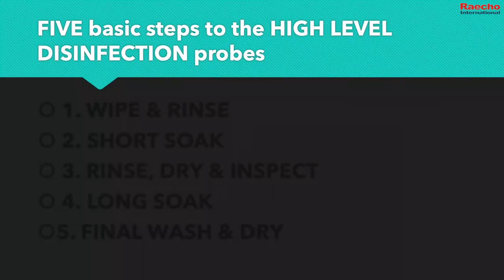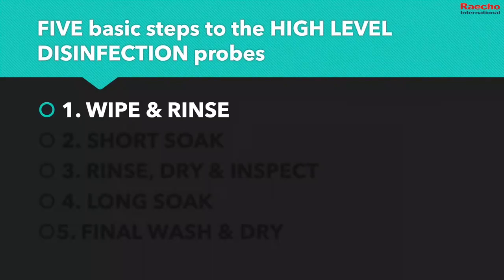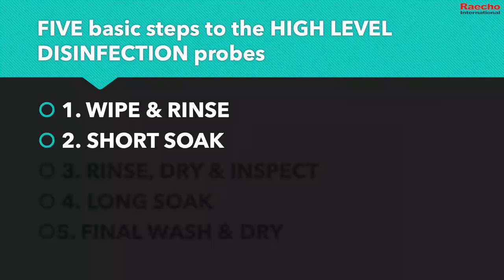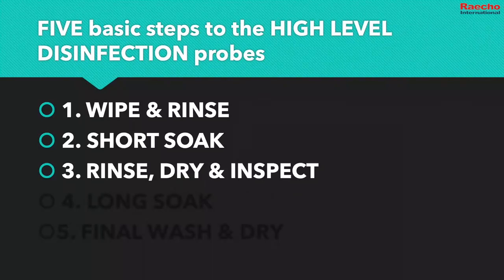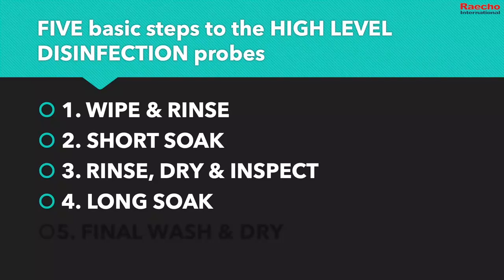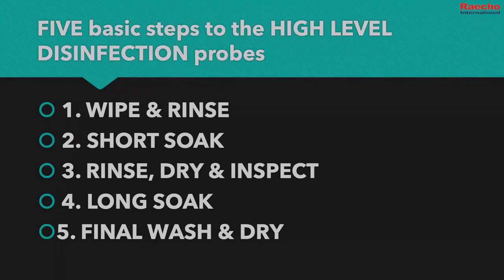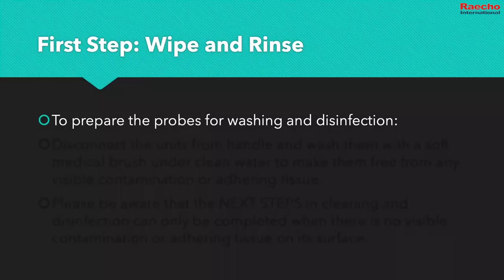There are 5 basic steps to the high-level disinfection of the probes: wipe and rinse, short soak, rinse, dry, and inspect, long soak, and then the final wash and dry. The first step is to prepare the probes for washing and disinfection.